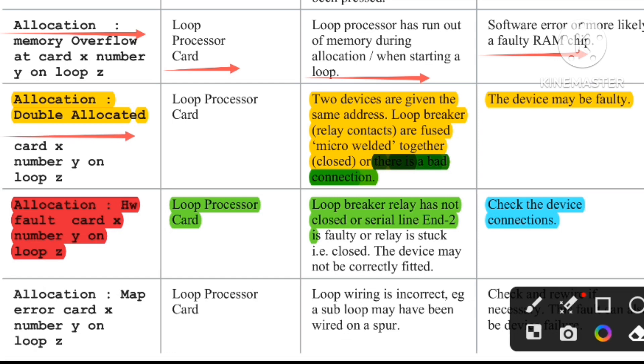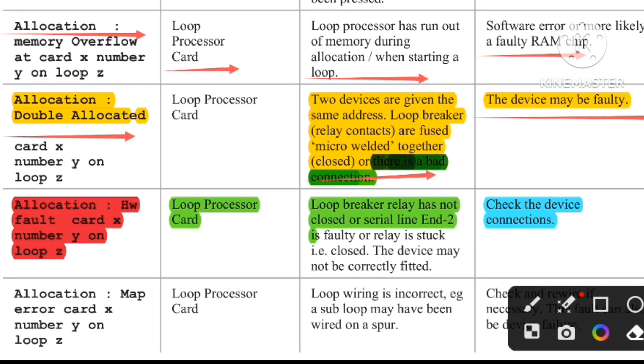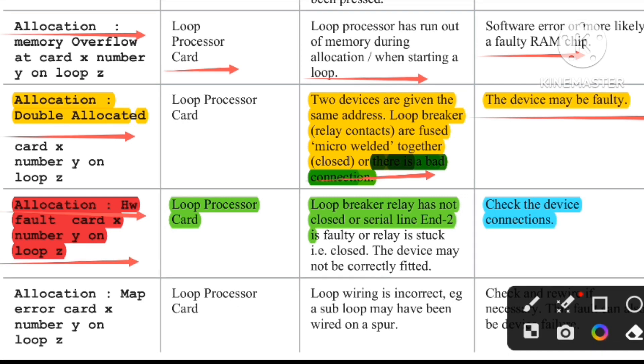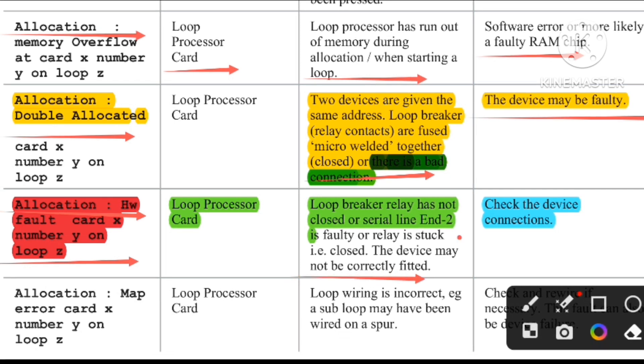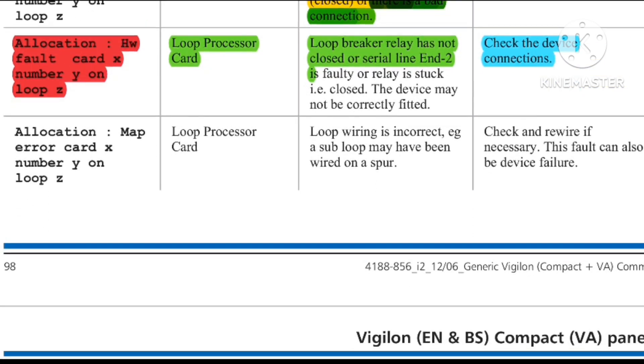The next faults visible in the menu: 'Allocation double allocated' — bad connection or faulty device, two devices given the same address. 'Allocation HW fault card X' — the device may not be correctly fitted. 'Allocation map error, card X, number Y, on loop Z' — another allocation-related fault visible in the Gent panel menu.